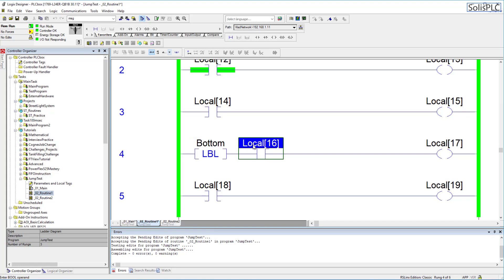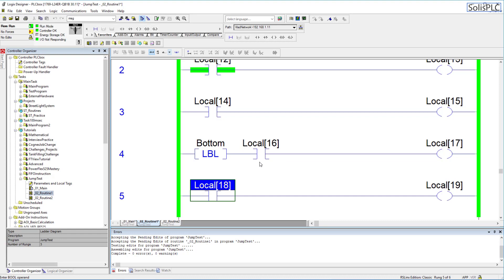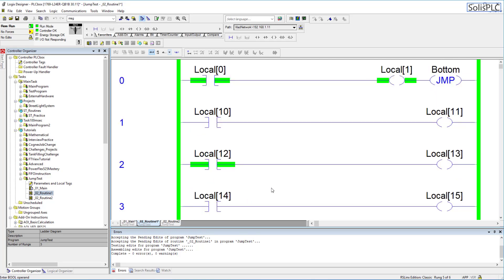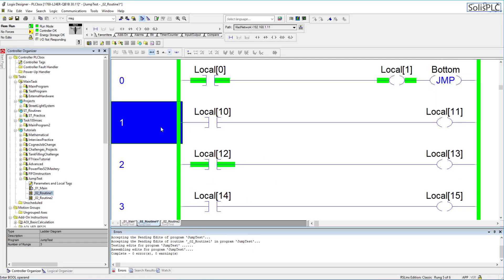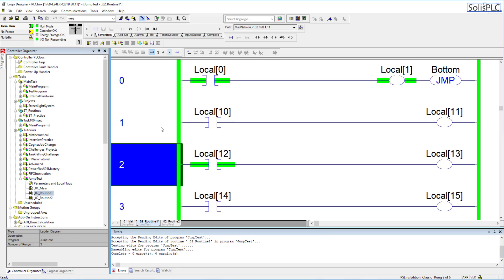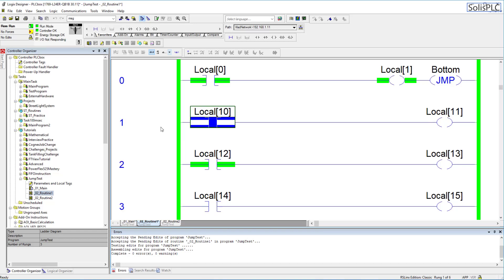So if I toggle this XIC as you can see it works as expected and there's nothing nothing different there same on this local 18 tag I can toggle that without any problems now that being said these rungs 1 2 and 3 are being skipped by the PLC program what this means is that regardless of this XIC value on this tag 10 12 and 14 the PLC is never going to execute them it's just going to bypass them and go to this rung number 4 where the label resides.